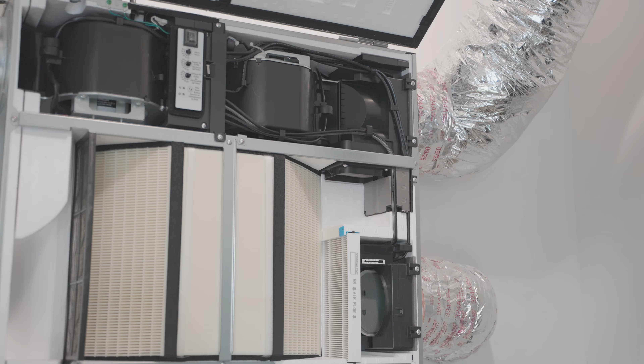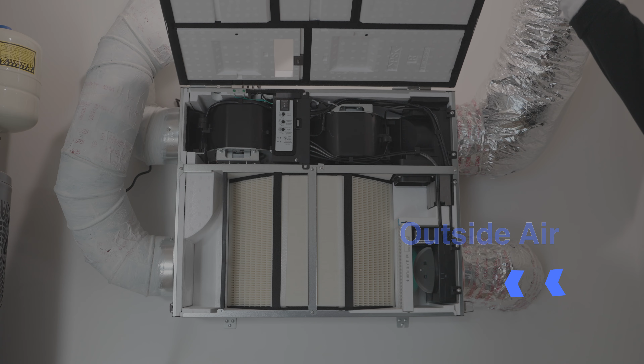We seek to eliminate uncontrolled air infiltration and exfiltration across the building envelope, while at the same time very intentionally bringing in air from a controlled source and exhausting stale air from inside of the home. Passive house projects use continuous mechanical ventilation with heat recovery. Here we're doing that with a machine called an ERV, or energy or enthalpic recovery ventilator, that brings in a calculated volume of air 24/7 while simultaneously exhausting an equal volume of air. Those two streams of air pass by one another, but they never touch.